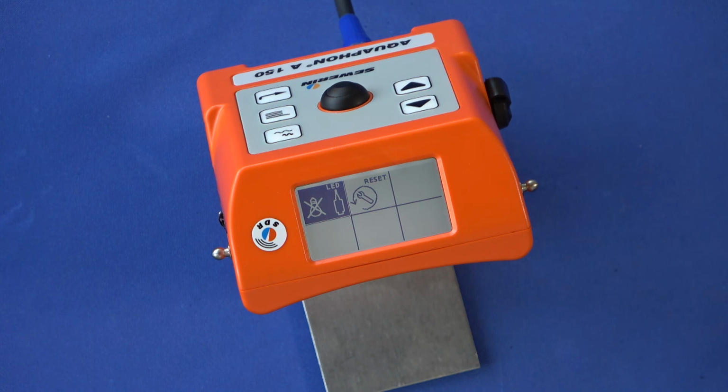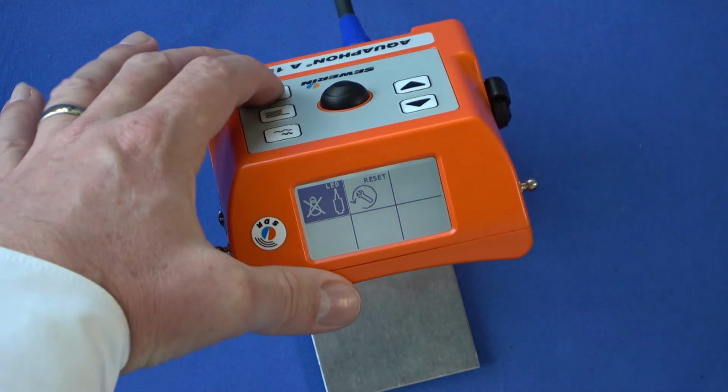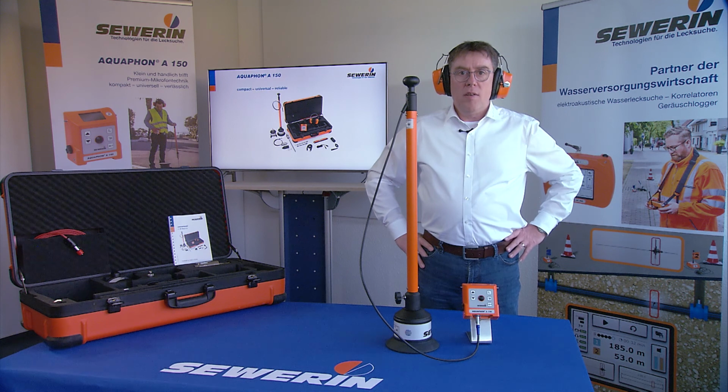If you press the Enter key again, you will get to the second page of the menu and find further options here. At the top left, you can specify where the flashlight function of the TM200 or UM200 should be activated. The reset function is on the right. This will reset the A150 to factory settings. You can exit the device settings at any time by pressing the menu button again. All device settings are permanently saved in the AQUAPHON A150.